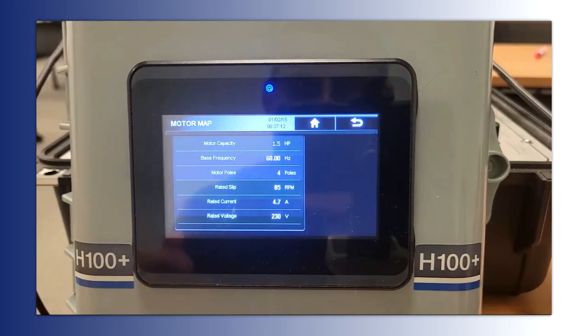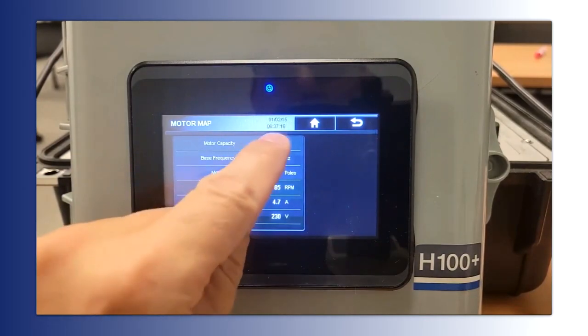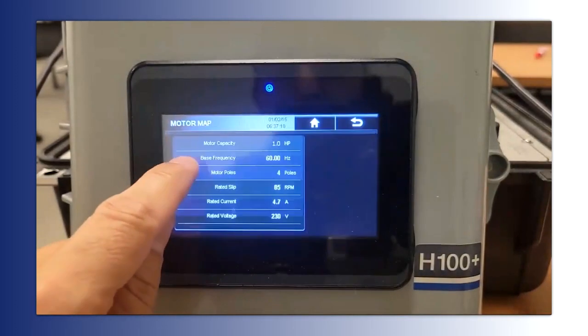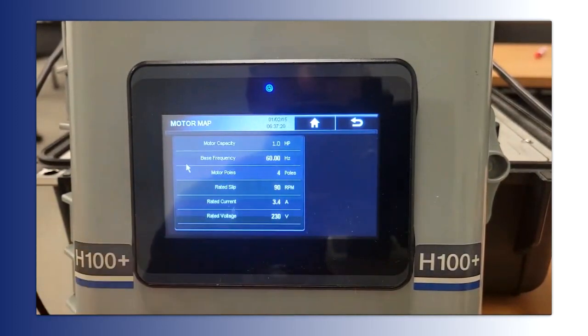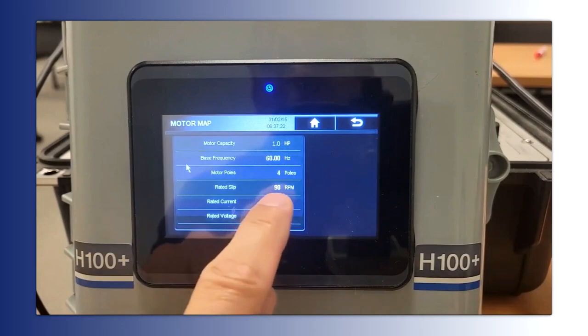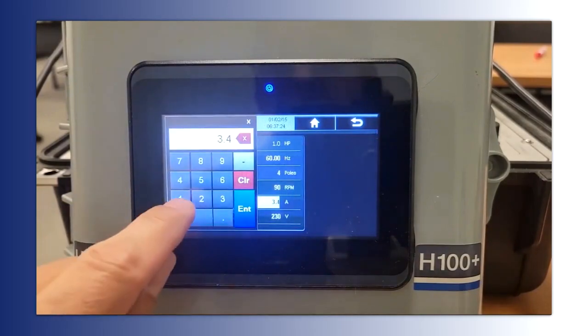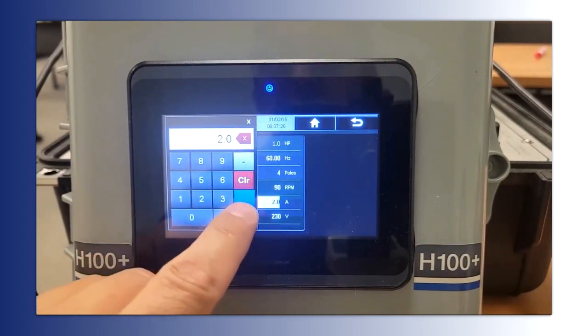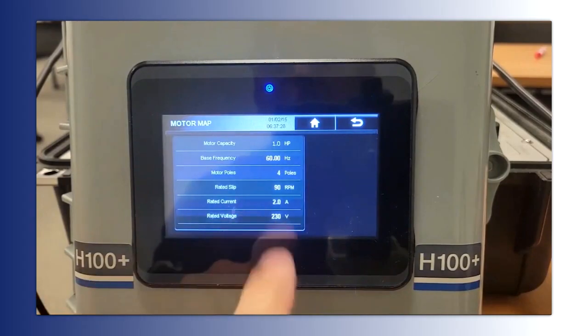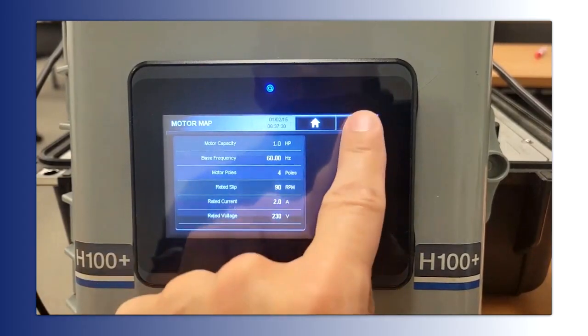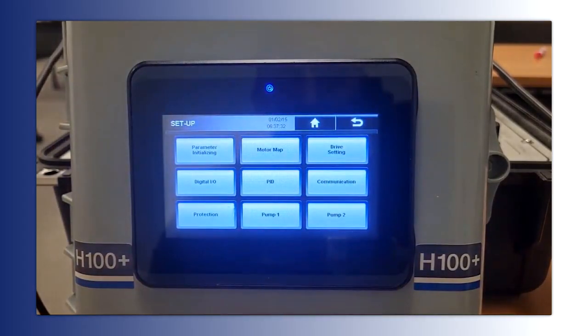And this is nice because it's just a point and click touchscreen. So if I want to change my motor capacity, I could just click it. Now I went down to 1 horsepower. I could go and change my rated current. Let's change it to, I don't know, 2.0 amps. There's your rated voltage, and then you could go back. And next thing, let's just see what this is set up for starting and stopping.